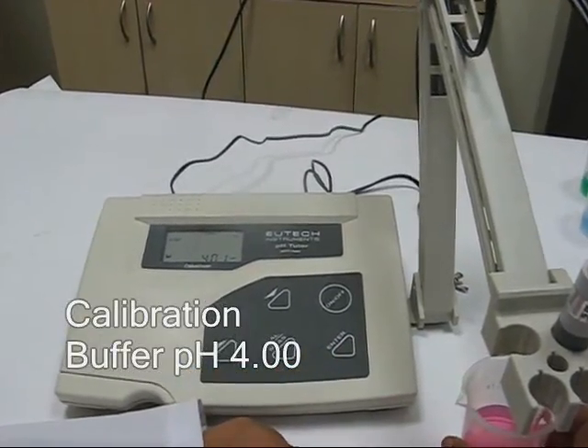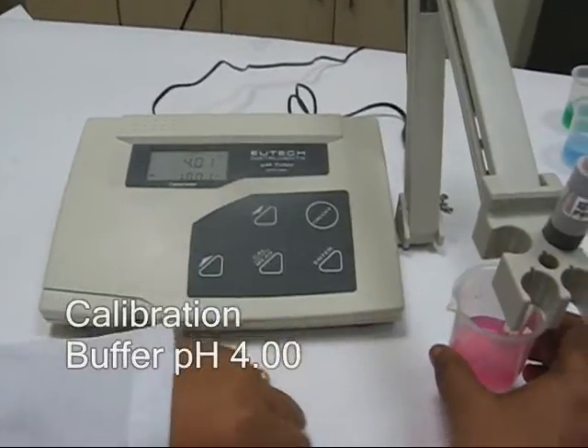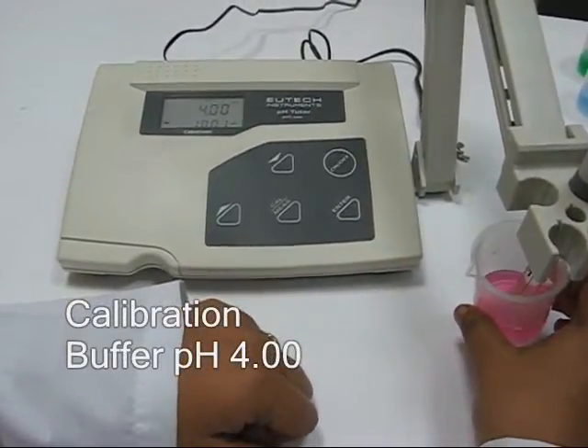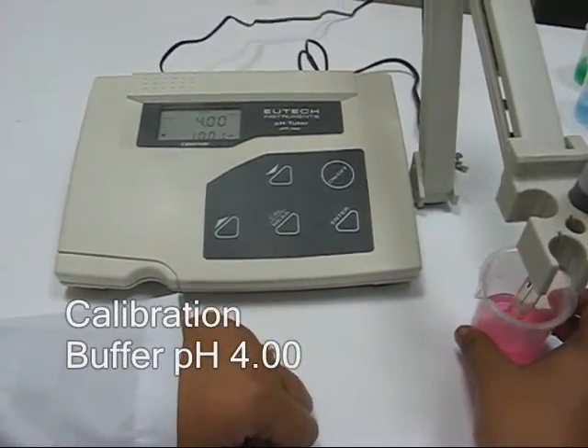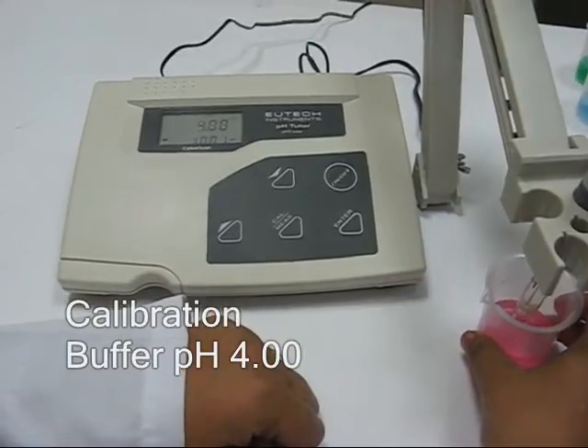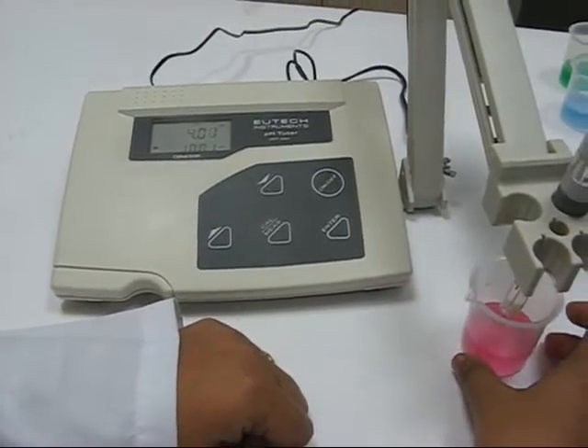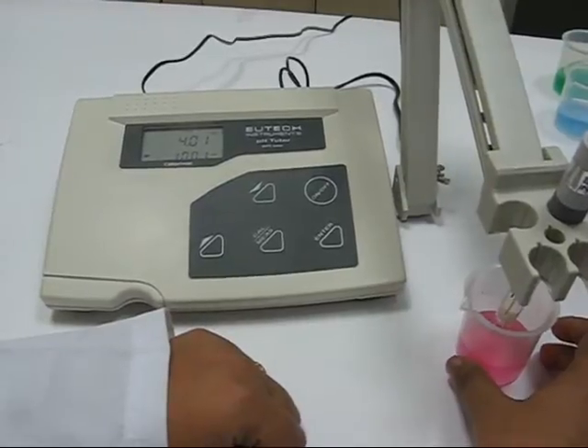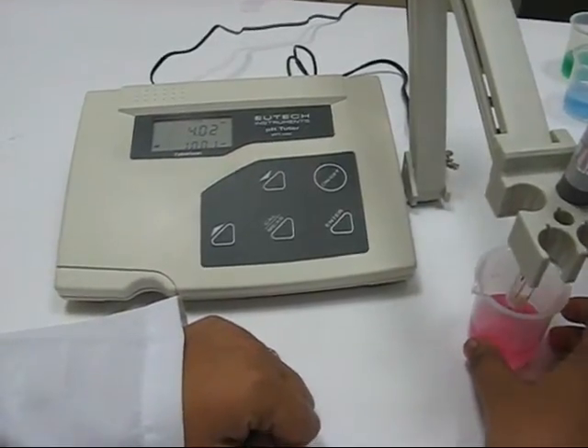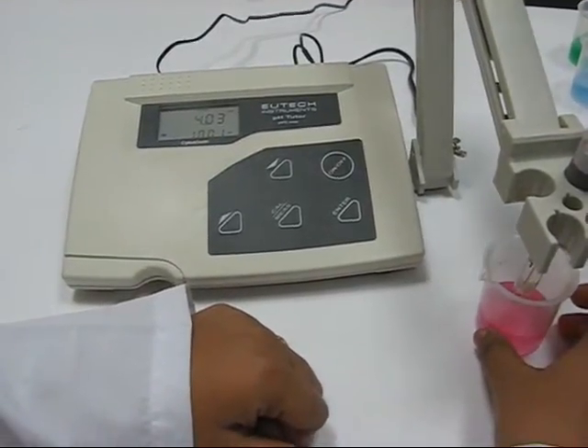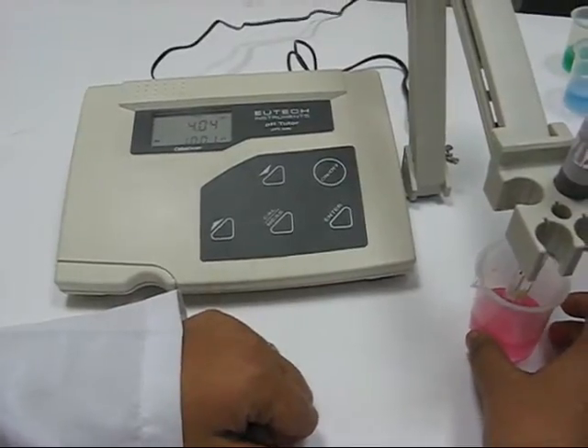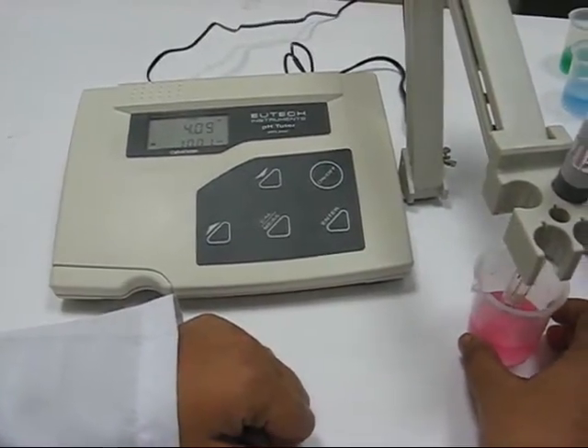The reading flashes, and now you have completed a 2-point cal. Now at this point you have the choice of continuing with the third point cal, which would be recommended in most of the cases. However, if you would like to stop here and get out to the measurement mode, you can do so by pressing the cal measure key. But we won't do that now. We will do a 3-point cal.